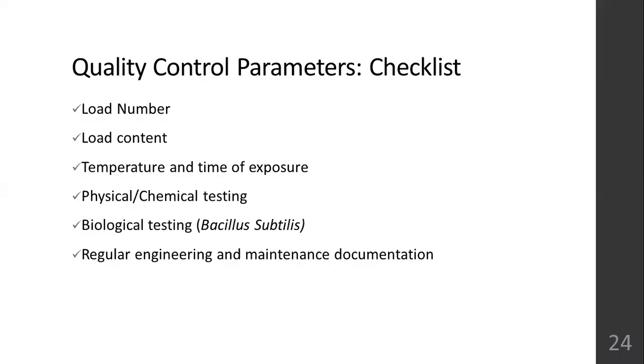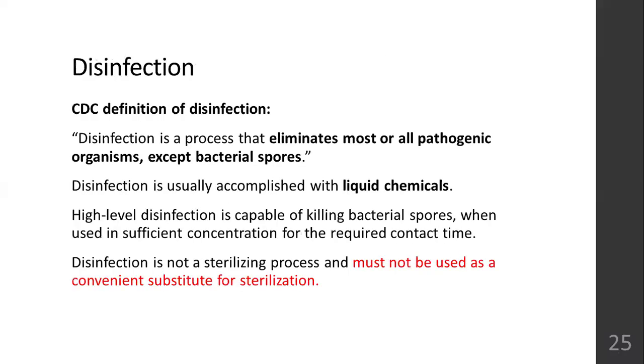Then the quality control parameters used: checklist, load number, load content, temperature, time of exposure, chemical or physical testing, biological testing, regular engineering and maintenance and documentation. These all are the parameters which should be mentioned on the sterilized item. Okay. Coming to disinfection, according to the CDC, disinfection is a process that eliminates most or all pathogenic organisms except bacterial spores.